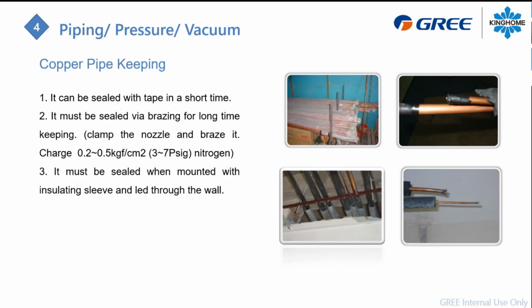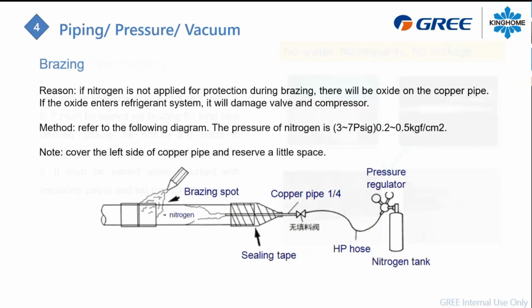Also, when you do your piping, make sure to have clean pipes. It's very important to not have impurities in your refrigerant line. So pay really good attention: if you do a pre-install piping set, make sure you flow some nitrogen into it, pinch it, braze it, and keep pressure in it, just to keep the impurities from getting inside the piping. This is really important.